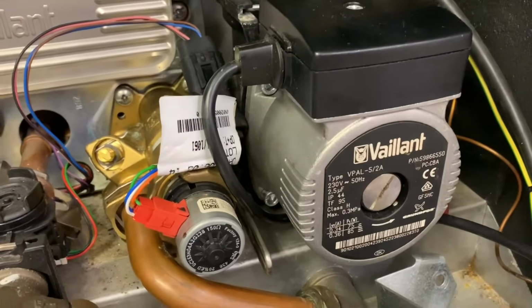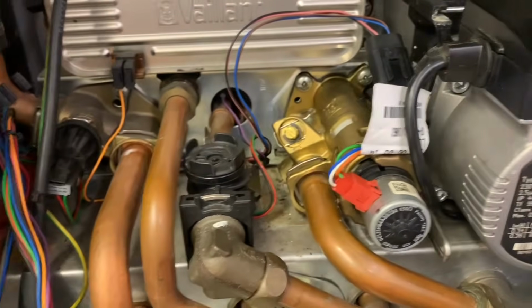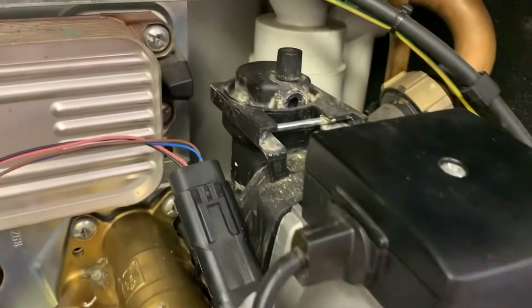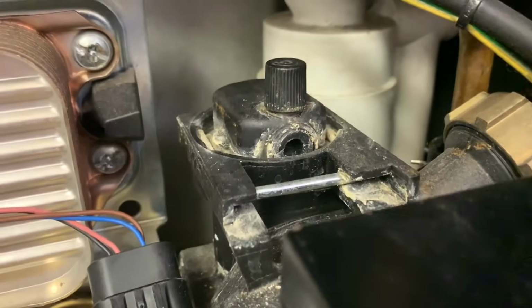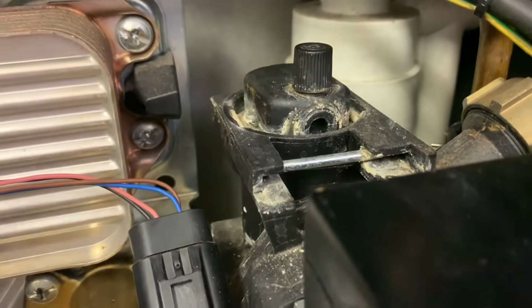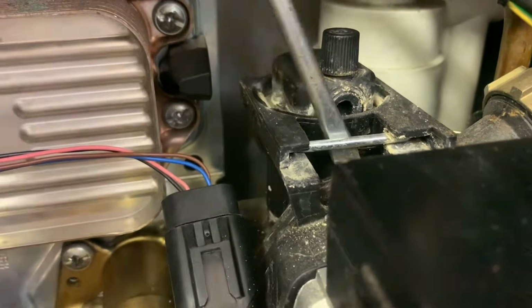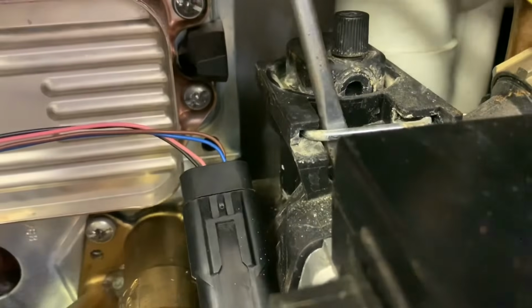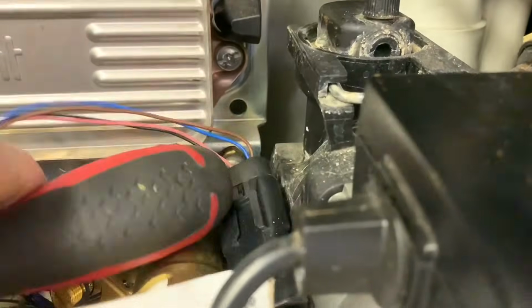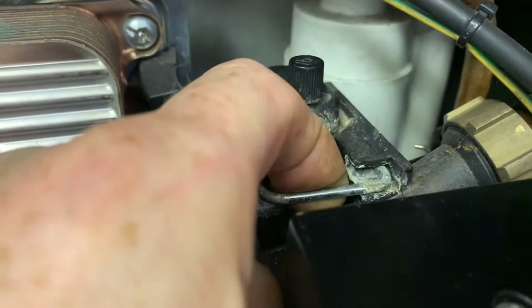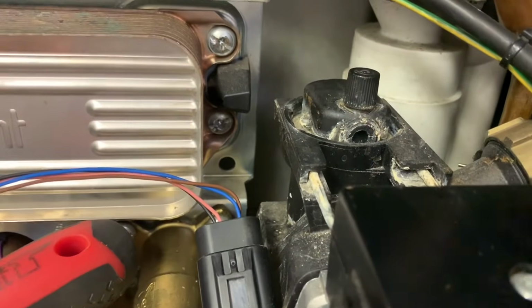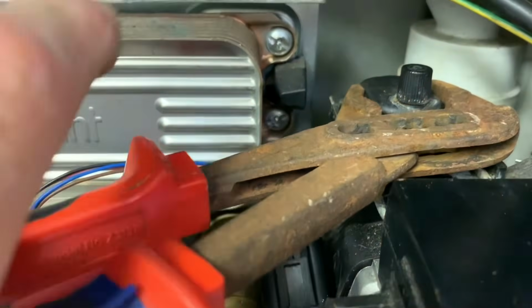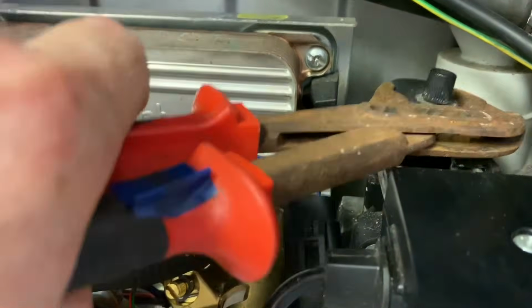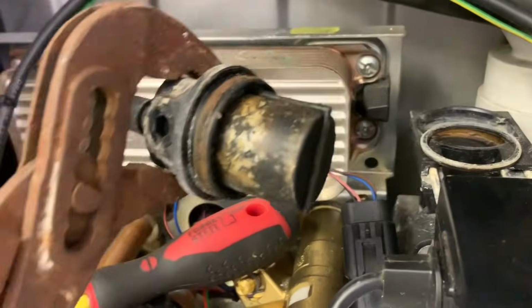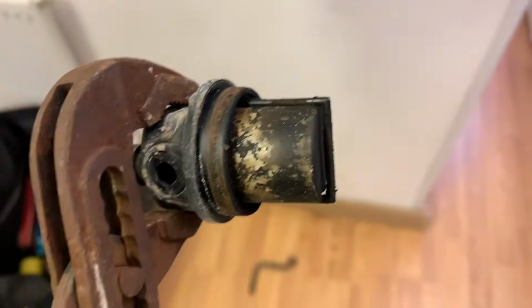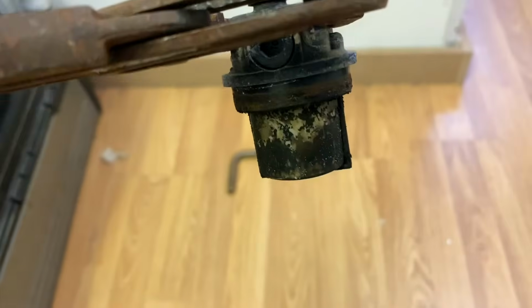Okay, so I've put a few things back in again. So you can see now how we're going to take off the crusty automatic air vent. So first of all, we need to get a flat screwdriver and prise this bar forward so it comes all the way out. Okay, and we need to get some grips on the flats that are there, and this should come up. You can now see the O-ring, and you can see how crusty that is.